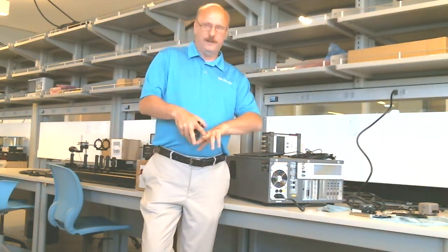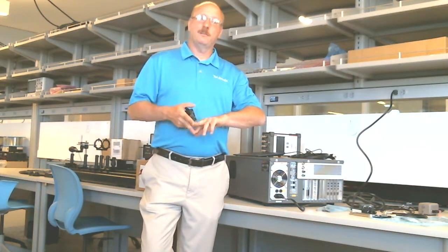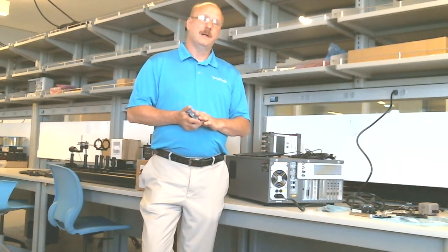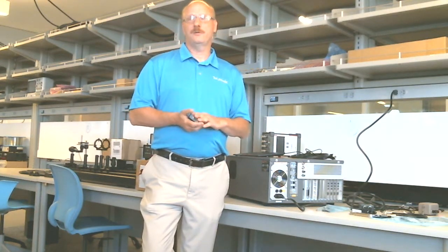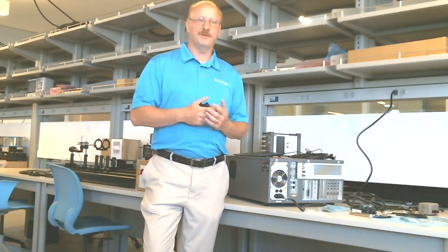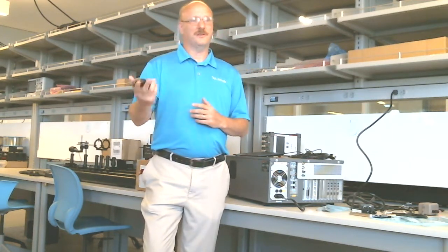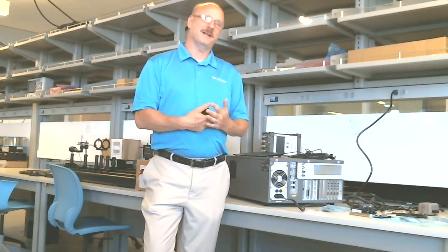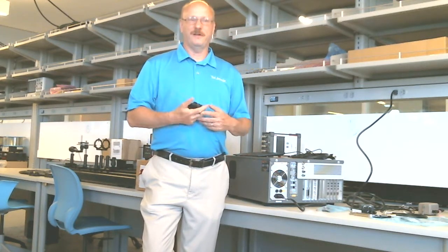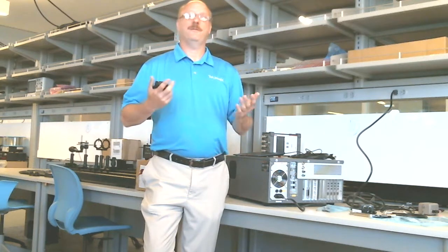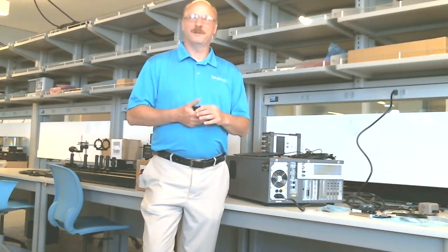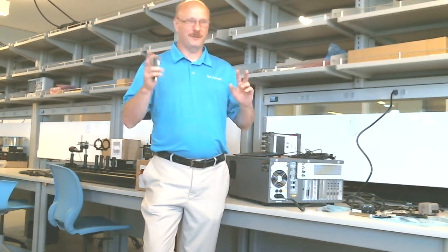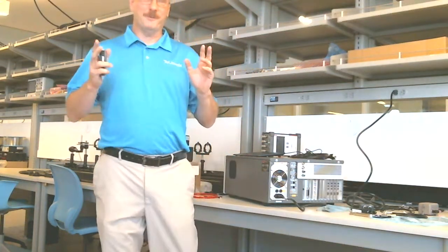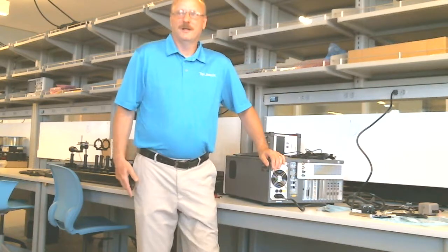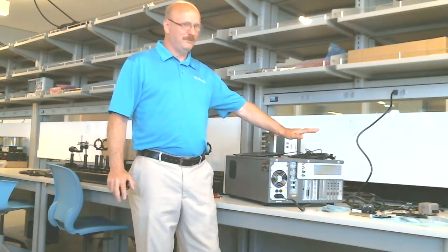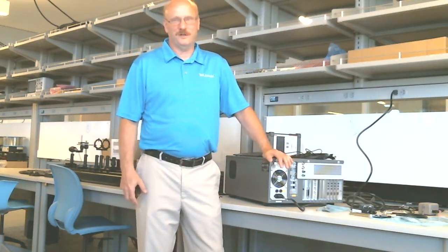But when you parallel, we don't recommend you parallel more than 2 channels, because now you run into the case where 2 channels can gang up on one, and you can damage the instrument. Now you can source twice the current into one unit than it can handle. In theory, in the factory, we've ganged up 5 of them, no problem, and it works. But we don't recommend it because if something goes haywire, your software, or you program it wrong, you can damage things. As long as you're not doing those kinds of things, you can't damage this box. It's pretty sturdy.